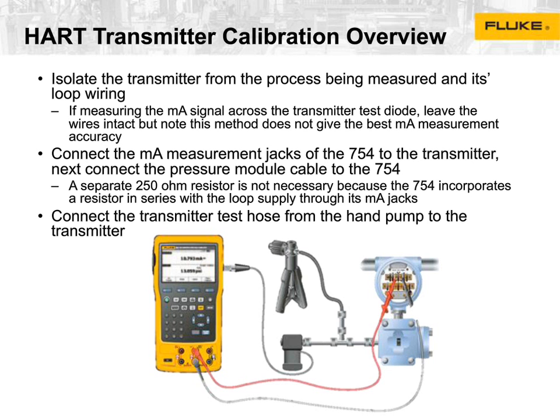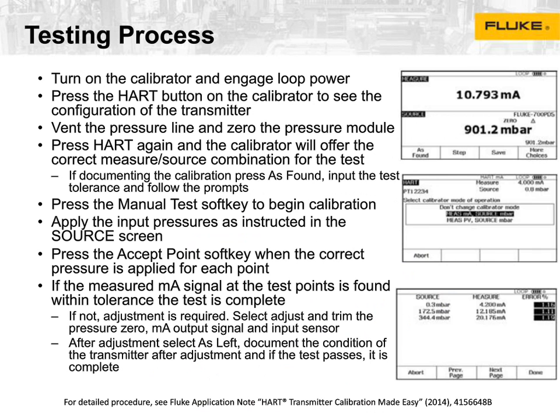Okay, the process is pretty straightforward. You're going to turn on the calibrator. You're going to turn on loop power. You're going to press the Hart button to see the configuration of the transmitter. I've got a picture of what that looks like right here. So that's the 10.793 milliamps, 901.2 millibar.